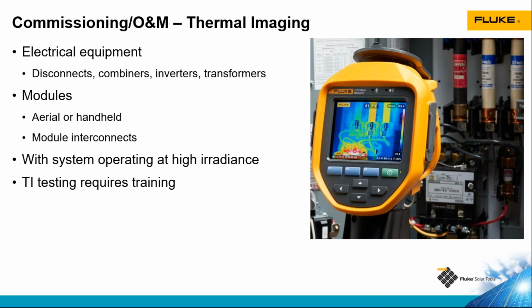When we're doing thermal imaging, we need to make sure that the system is operating at a high capacity. So we want a higher irradiance or intensity of the sunlight, so there's a lot of current flowing through the system that will allow us to see things that are hotter than they should be and things that are cooler than they should be.